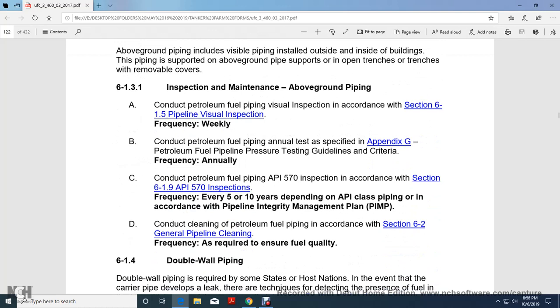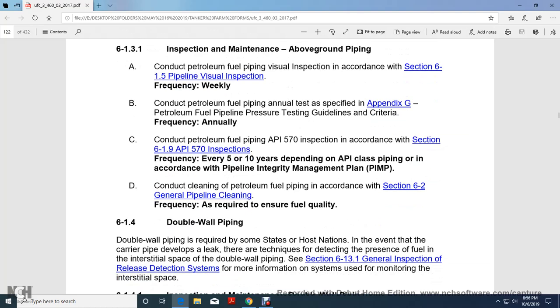Conduct the petroleum fuel piping annual test specified in Appendix G, Petroleum Fuel Pipeline Pressure Testing Guidelines, criteria frequency annually. Conduct the petroleum fuel pipeline inspection in accordance with the American Petroleum Institute API 570, per 6.19, API 570 inspection, frequency every 5 to 10 years depending on the API piping class, in accordance with the pipeline integrity management plan.